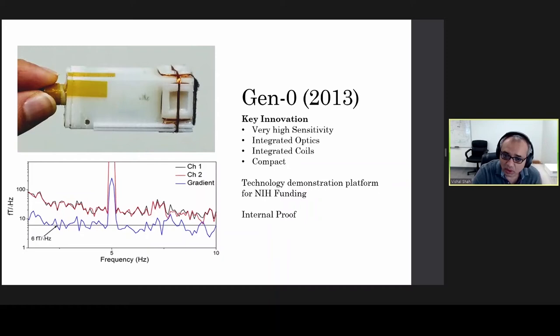The prototypes were sufficiently compact, and they had integrated optics and coils. And these things made the sensors usable, easily usable, and one could place them over the head and start recording MEG data. And this graph here shows auditory evoked responses that were obtained with these Gen Zero prototypes. The signal to noise ratio of the response was just as good, if not better, than what we measured with a squid-based MEG system. And so these results convinced NIH to fund the next bigger phase of funding.